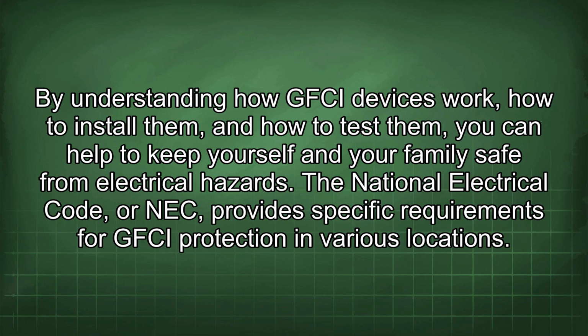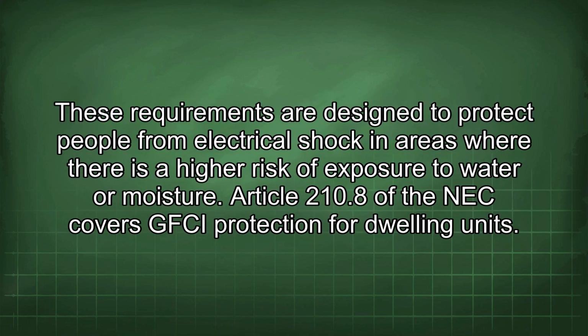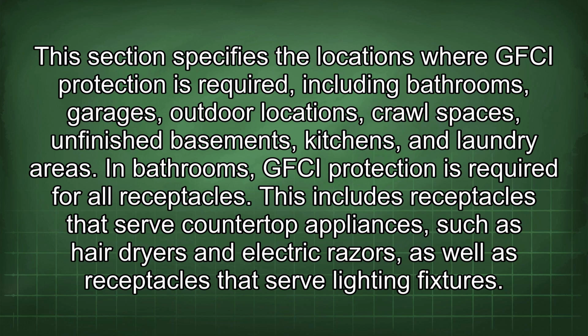The National Electrical Code, or NEC, provides specific requirements for GFCI protection in various locations. These requirements are designed to protect people from electrical shock in areas where there is a higher risk of exposure to water or moisture. Article 210.8 of the NEC covers GFCI protection for dwelling units. This section specifies the locations where GFCI protection is required, including bathrooms, garages, outdoor locations, crawl spaces, unfinished basements, kitchens, and laundry areas. In bathrooms, GFCI protection is required for all receptacles.